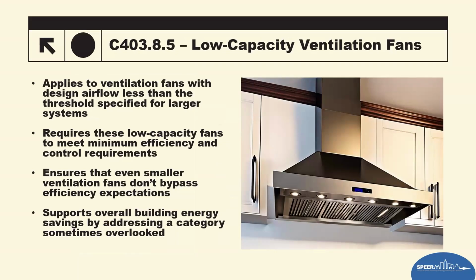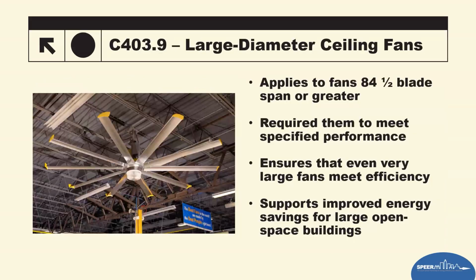There are specific requirements now. This used to be contingent in the code if you're looking at ventilation fans, but now we have something called a low capacity fan. There's now a specific section for that. It's dedicated to where these are not exempt from efficiency or controls. It ensures that the smaller units still incorporate automatic controls such as shut-off ventilation when demand is reduced. It also reduces the fan power limits. This basically helps maintain energy efficiency for smaller equipment instead of just tackling those large units that we see. So something that falls outside of what's called a large ventilation system still also now has a specific requirement section. And they've also addressed this as well.